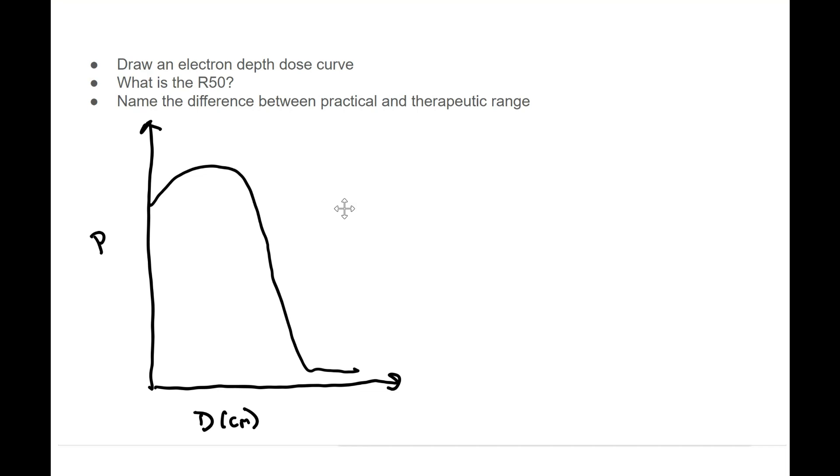Now R50, R50 is the depth where dose falls to 50% of its maximum point. So all you have to do is look over here on your percent depth dose and look at...